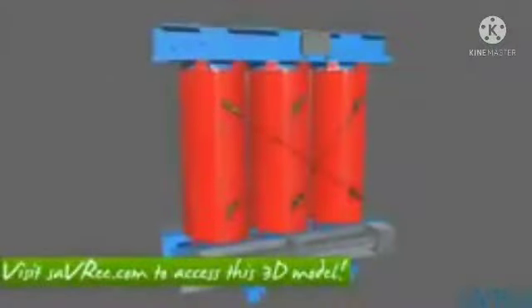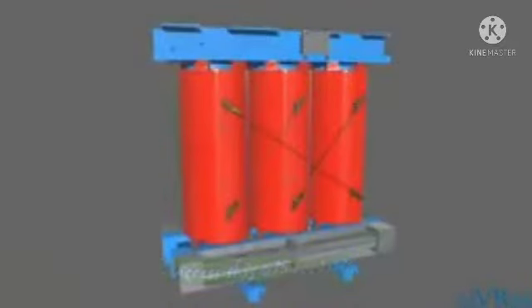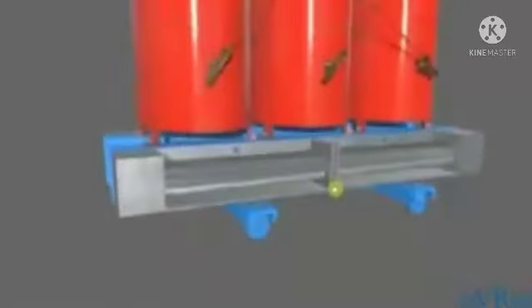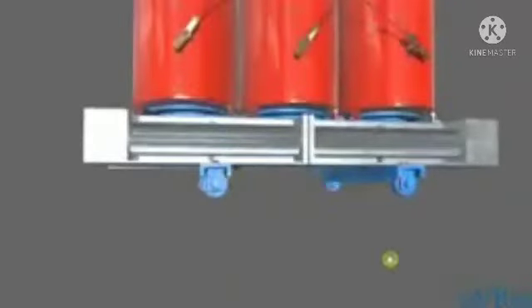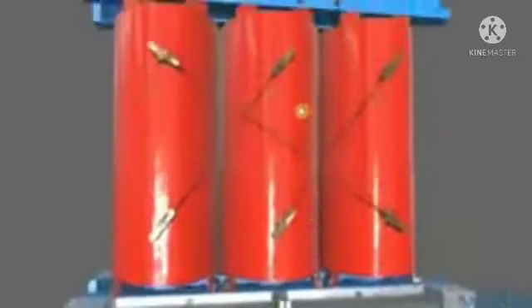So now you can see we're looking at a dry type transformer. This is a type of transformer that is not insulated by a liquid, and the liquid may be oil or perhaps some sort of synthetic oil or even a biodegradable type of oil. But either way, this is a dry type transformer, also sometimes referred to as a cast resin type transformer. We can see it's got wheels on the bottom for moving it into position, and we've got these grey pieces. These are for cooling the transformer.